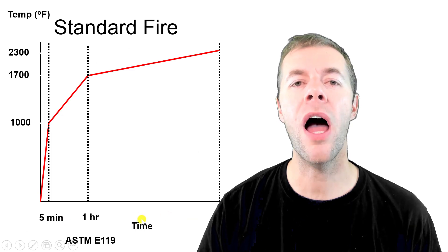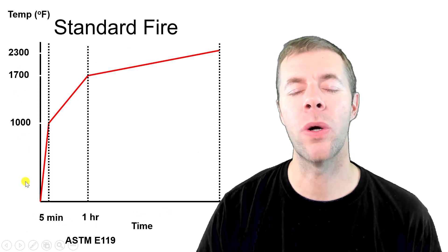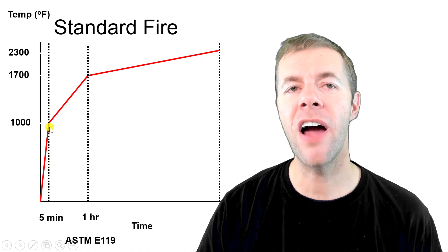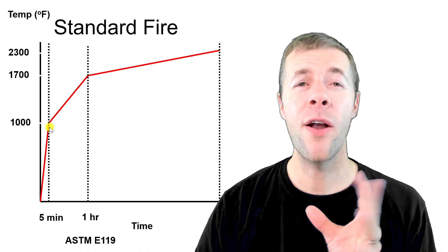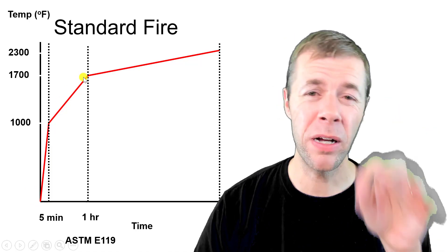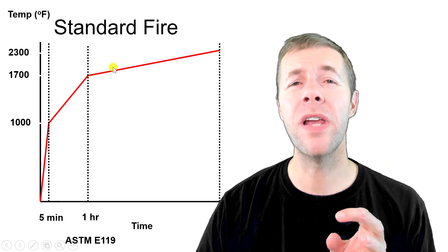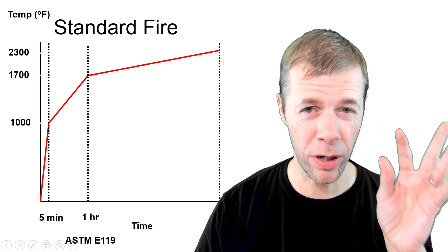On the x-axis I'm showing time and on the y-axis I'm showing temperature. Over the first five minutes the temperature goes up to about 1,000 degrees Fahrenheit, over the next hour it goes up to about 1,700, and over the next eight hours it goes up to 2,300 degrees Fahrenheit.